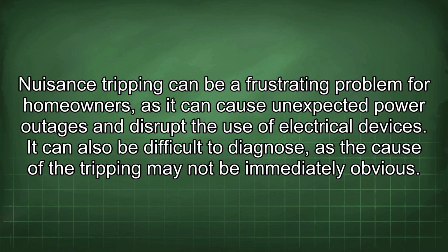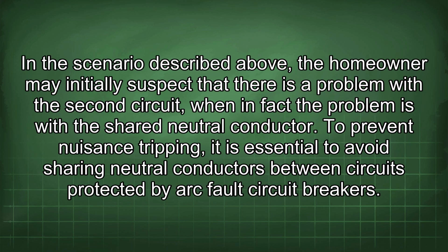Nuisance tripping can be a frustrating problem for homeowners, as it can cause unexpected power outages and disrupt the use of electrical devices. It can also be difficult to diagnose, as the cause of the tripping may not be immediately obvious. In the scenario described above, the homeowner may initially suspect that there is a problem with the second circuit, when in fact the problem is with the shared neutral conductor.